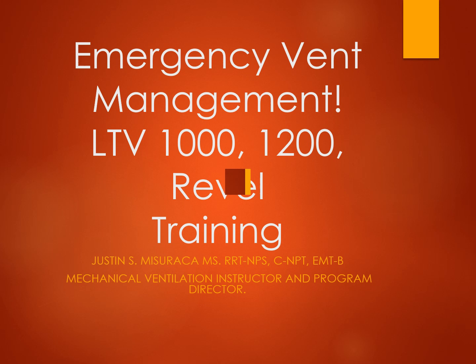All right, sensitivity. I don't know why you guys are not sensitive to my needs. If you take a look at the sensitivity on the LTV 1000, the 1200, and the Revel NV, it's dialed in based on liters per minute. So it's not 1 liter. If your sensitivity was set at 1 liter, it doesn't mean they have to pull back a liter. It means they have to pull back what would be a liter going through, what that flow would feel like if it was a liter. I guess that's probably the easiest way to understand that.